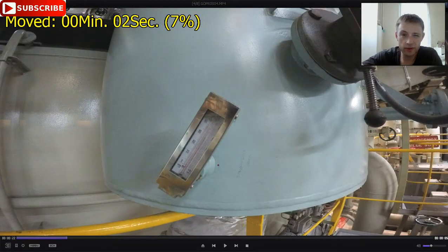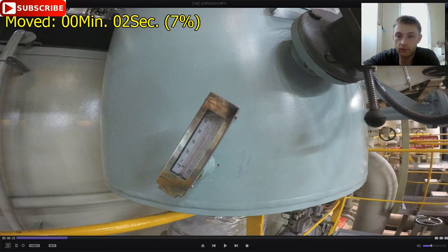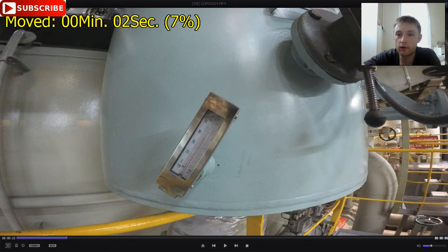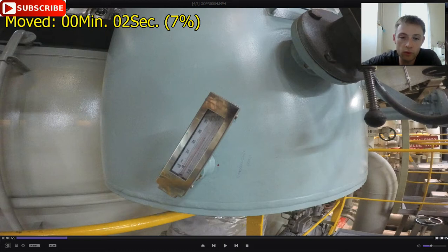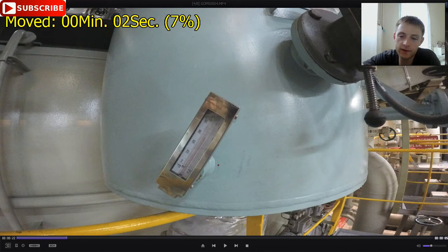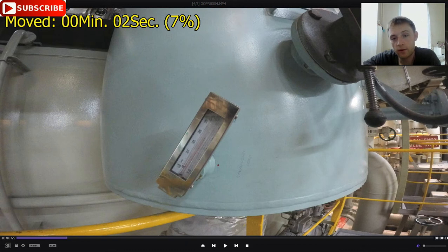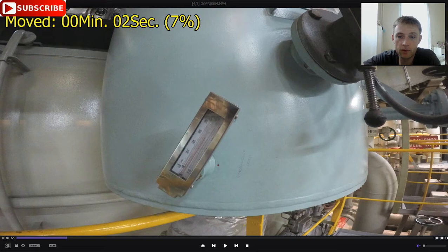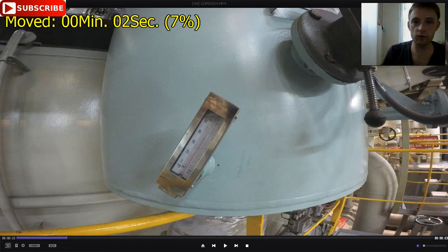Hello everyone, this is AdventureStory and today we will talk about condensate temperature — the condensate temperature of the main condenser, where the steam exhaust from the cargo turbines falls down. As you can see, the temperature is 60 degrees Celsius. We have two cooling pumps running: one main cooling sea water pump and one smaller auxiliary cooling sea water pump.